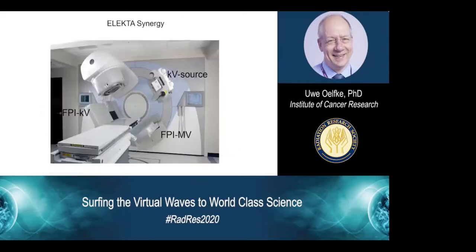Just to repeat, the standard configuration for X-ray guided radiation therapy: we have a kilovoltage X-ray source mounted to the gantry of a linac and an extra detector, and the imaging beam is mounted perpendicular to the treatment beam, where you have a second flat panel imager for detecting the transmitted radiation through the patient.